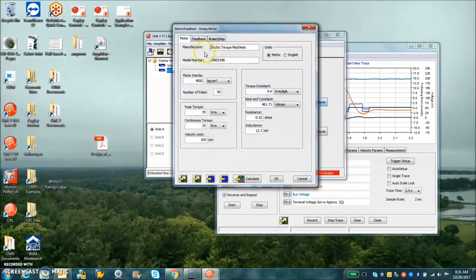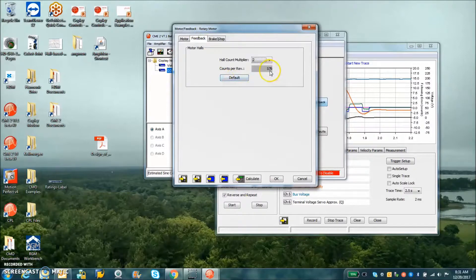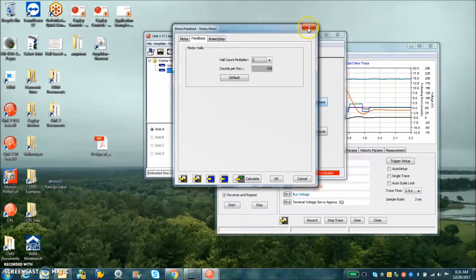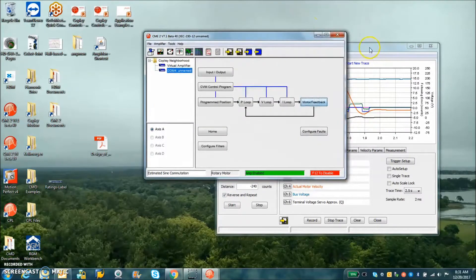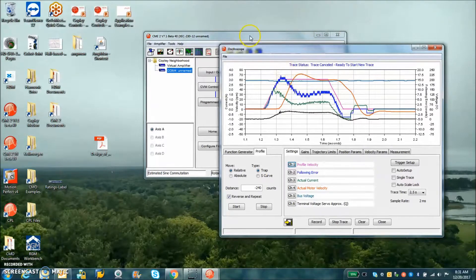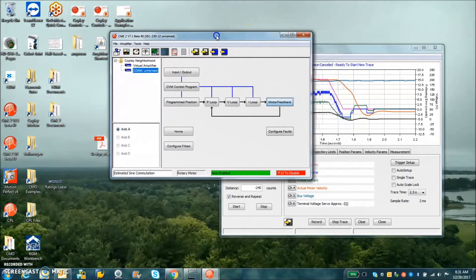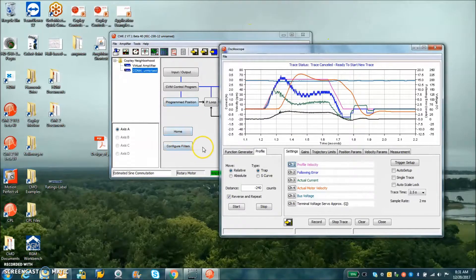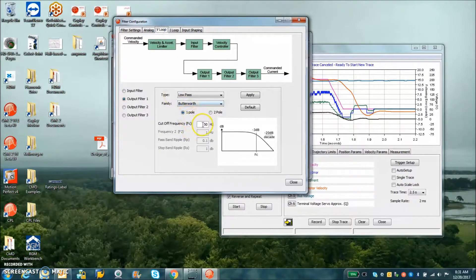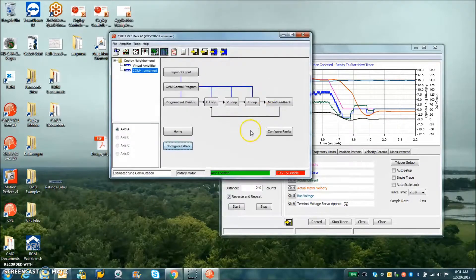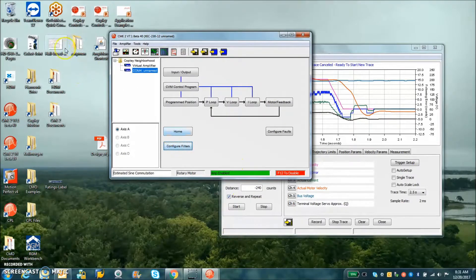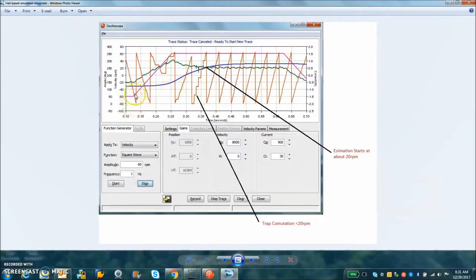The hall counts per rev on the feedback is 576 counts per rev. An encoder would do much better but we're just winging it with just halls here today. I did move the filter in single pole 50 hertz because my inertia is huge, there's no unnecessary bandwidth there. We'll take a quick peek at this estimated velocity.